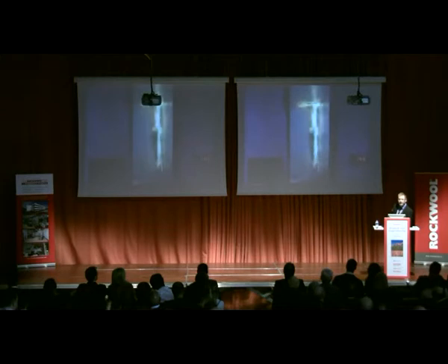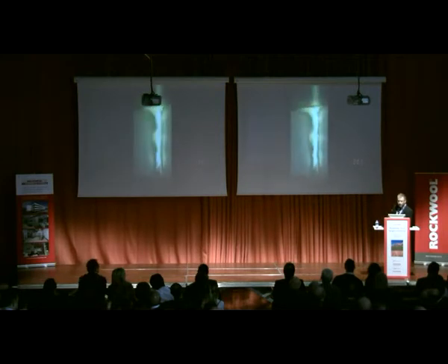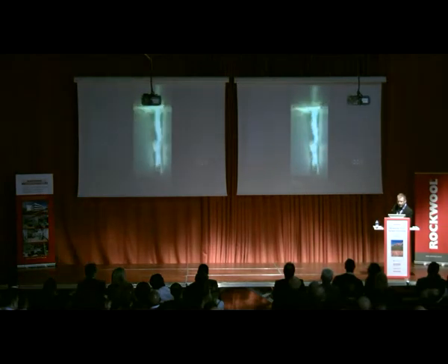In SBI, it's 30 kilowatts. So this is more realistic, and after 10 minutes, the heating power is increased to 300 kilowatts. So as you may expect, nothing really happens to stone wool core sandwich panel as non-combustible construction.